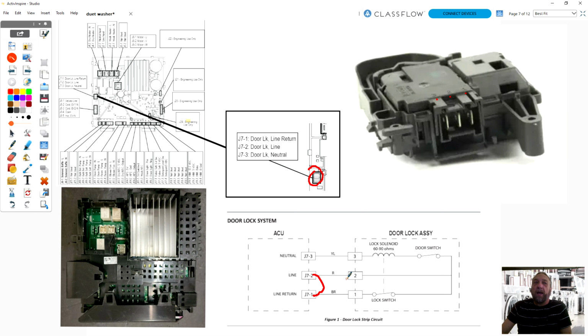No. You can. Remember, this is line, and they're saying line return. Basically, this is line voltage to feed the solenoid, but this is line voltage coming back. We have no load here. You see this has a solenoid here? If you look at the circuit on the bottom, if you look from red to brown here, do we have a solenoid or a motor or a light bulb or any load in that circuit? No, just a switch. Just a switch.